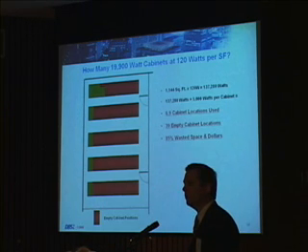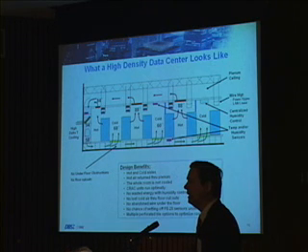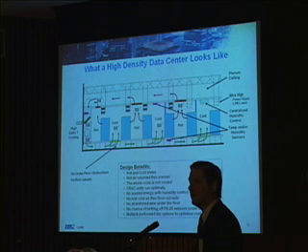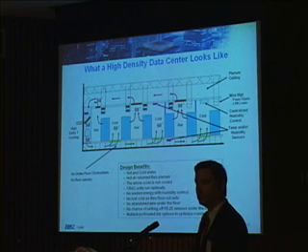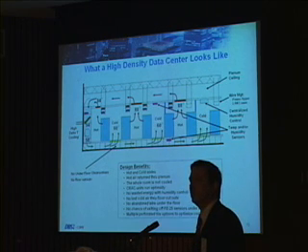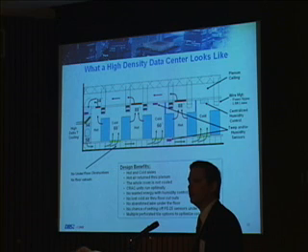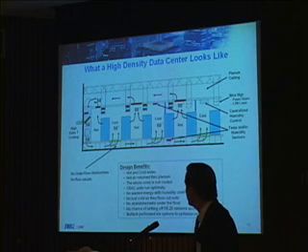To be able to do that, we've got to completely redesign the data center. And this is one of the floor plans of what a high-density data center would look like. We've taken the floor height from 6 to 12 inches and raised it to 30 inches. So now I'm 30 inches off your concrete floor. In most cases, I run out of ceiling height room in a lot of data centers to stay compliant with NFPA, the sprinkler requirements for distances, or if you're FM200 or FE25. There's not enough headroom in a building to do this higher data center floor.